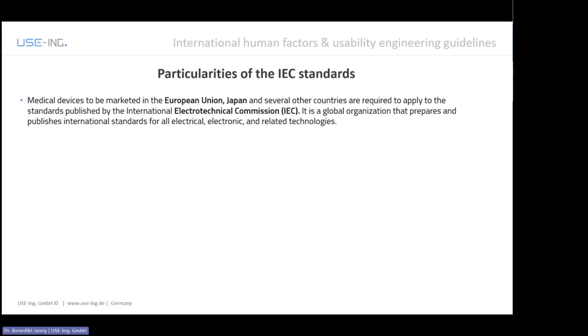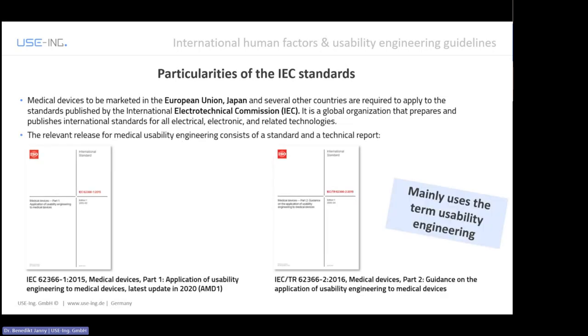The relevant release for medical usability engineering consists of a standard document, the IEC 62366-1, titled Application of Usability Engineering to Medical Devices. And there's a supplemental document, the technical report called IEC TR, for technical report, 62366-2, which is titled Guidance on the Application of Usability Engineering to Medical Devices.